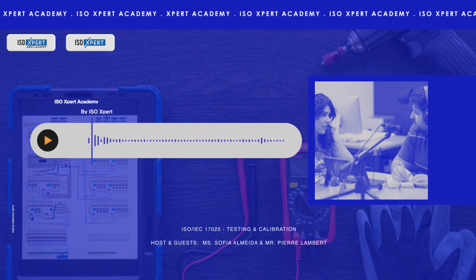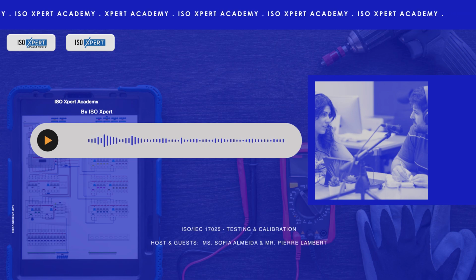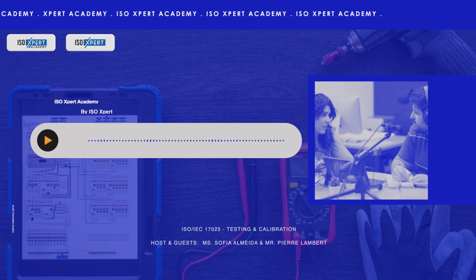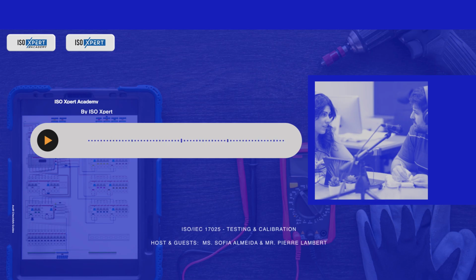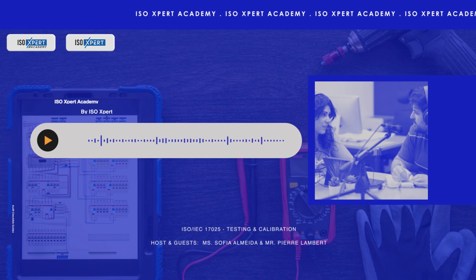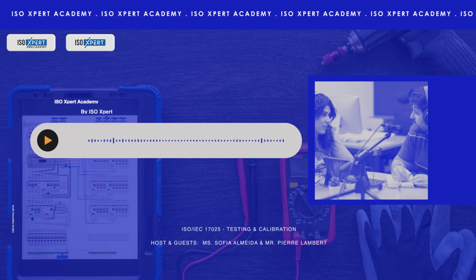It begins, according to Clause 7.1, with a really meticulous review of requests, tenders, and contracts. Before any testing starts. Absolutely. Before any work begins, a lab must clearly understand and thoroughly document the customer's requirements. What do they need tested? What specific method? What are the acceptance criteria? Why is that so critical up front? It's crucial for preventing misunderstandings and for ensuring the lab can actually do what the customer needs accurately and reliably. Auditors would look for evidence like thorough job orders, detailed quotes, and formal review forms that show this upfront clarity and agreement.